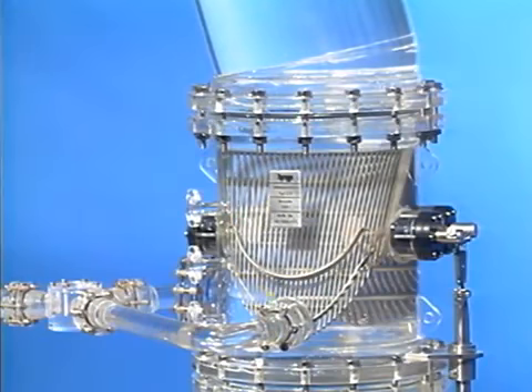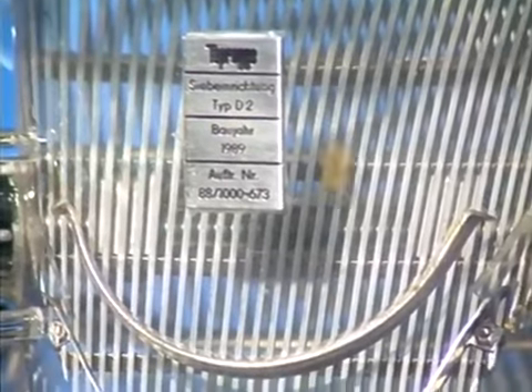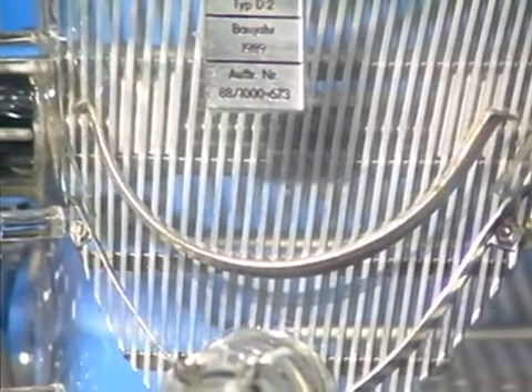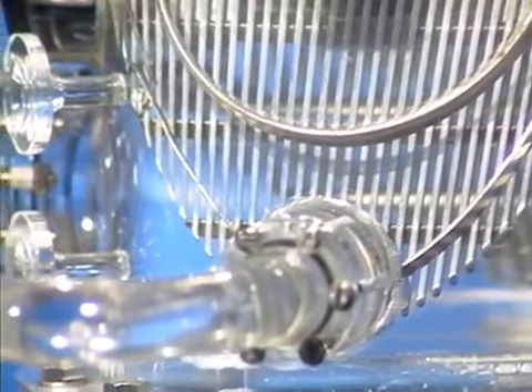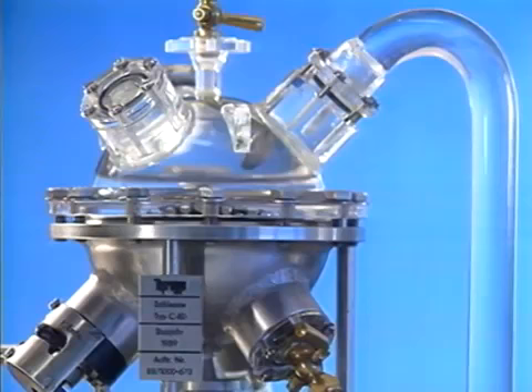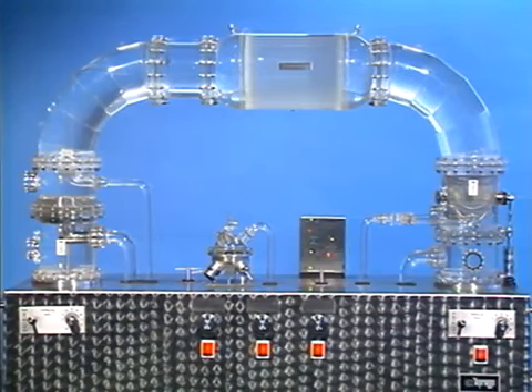At the condenser outlet, the sponge rubber balls are removed from the cooling water system by the strainer screens, and returned to the condenser inlet by the recirculation unit. A closed cleaning circuit. The TAPROGGE system cleans the condenser continuously online during actual operation. A simple and effective solution.